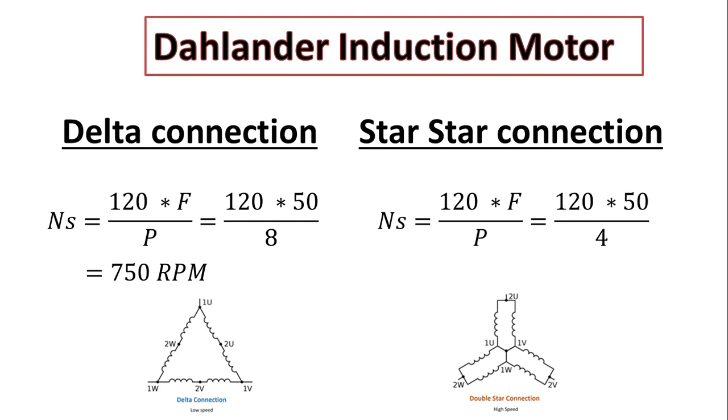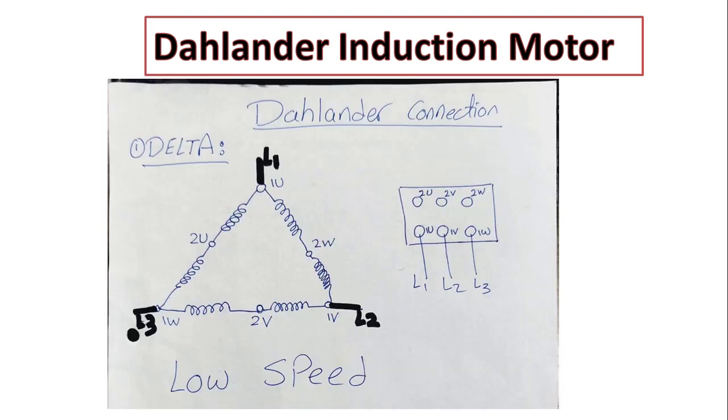So the synchronous speed will equal to 1500 RPM. Perfect. Now let's see how to connect the motor as star-star or delta. At first, if we connect it as delta, we will get the low speed because we will get here eight poles.